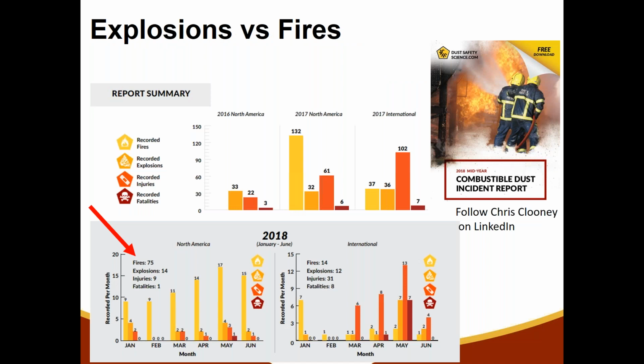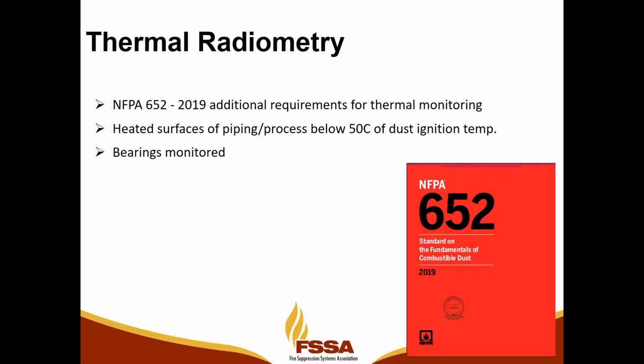All right. Now, in looking at the reports provided by Chris Cloney at dustsafetyscience.com, his reports are very helpful in analyzing the industry. We see that fires are happening about 3/4 of the time, and explosion events are about 1/4 of the time. So we're looking outside of the equipment itself and looking at the space where the combustible dust can be present. NFPA 652 for combustible dust, which came out in 2019, requires thermal monitoring of anything in the space where there's combustible dust that can reach combustion temperature. That's pipework, processes, bearings, motors, anything.